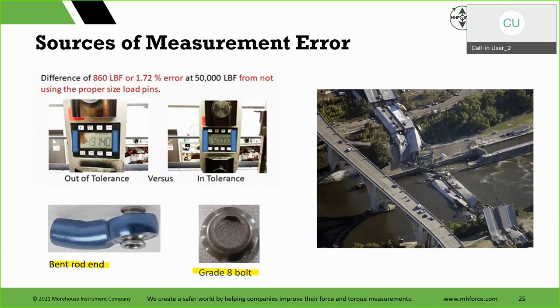What you do today, the measurements you make, make a huge difference. And things to consider: the output of the force measuring device can be significantly impacted by adapters, which pose serious safety concerns and can impact your measurement uncertainty. If you're sitting there with old adapters, consider the lifespan of them, how many times have they been loaded. Eccentric force and side loading. Calibration setups that do not replicate application. Said it several times, gonna keep saying it. Permanent material deformation. Is someone using something that's beat up? Not using ISO 376 recommendations for tension loading. ISO 376 is an international standard. It has a nice annex on what you should do for tension loading. Introducing unwanted bending or torsion. Would you know you introduced it in your machine?